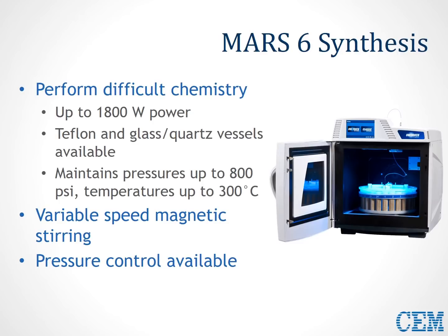You can choose from Teflon or glass vessels for small or large scale. Variable speed magnetic stirring is a standard feature in all Mars 6 synthesis systems and is highly recommended for any synthetic reaction. The custom-engineered microwave cavity of the Mars 6 synthesis is constructed of high-grade solid steel with a heavy-duty spring-mounted door with safety interlocks. So should an accident occur, students are out of harm's way as the incident is contained within the cavity, and the instrument will turn itself off to prevent any further damage.